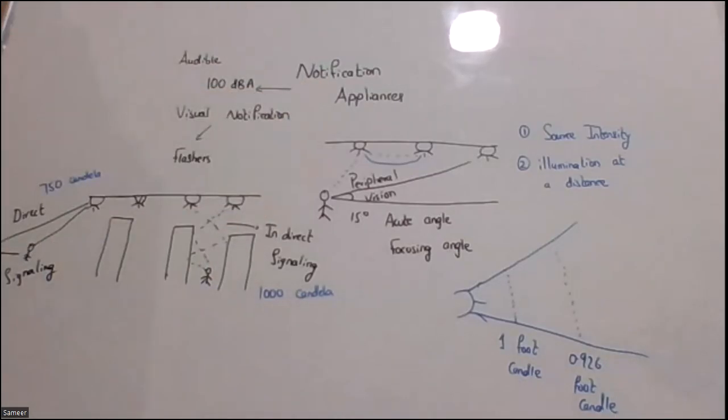And at the end of the conical view, if there are any environmental changes, it greatly affects the visibility. So for that purpose, it is very important to know what candela effective is usually required by us. Candela effective is the amount of illumination reaching a point towards the human eyes that can provide the sense of threat.